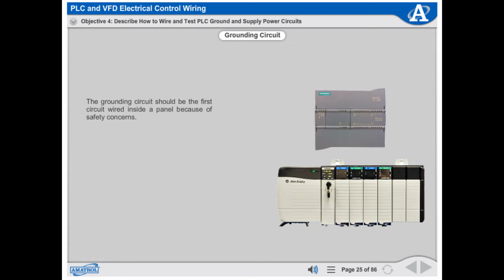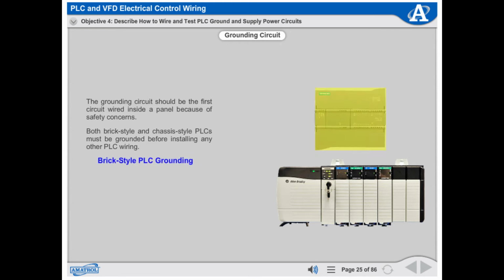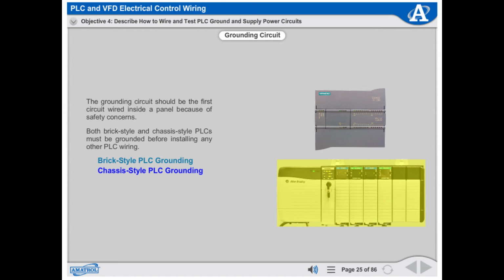The grounding circuit should be the first circuit wired inside a panel because of safety concerns. Both brick-style and chassis-style PLCs must be grounded before installing any other PLC wiring. Brick-style PLC grounding and chassis-style PLC grounding.